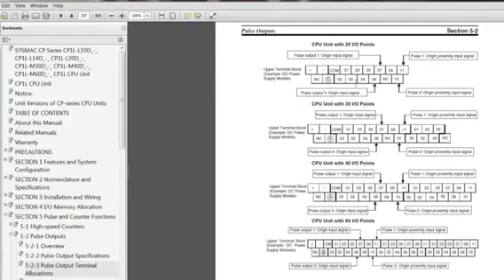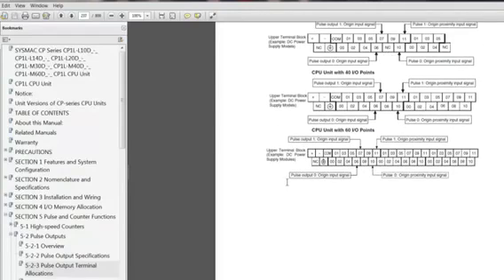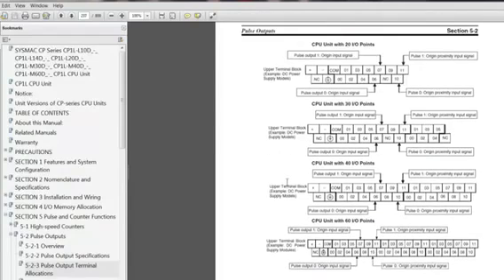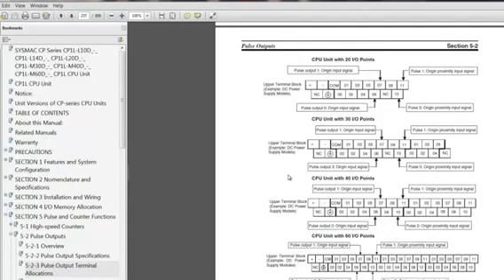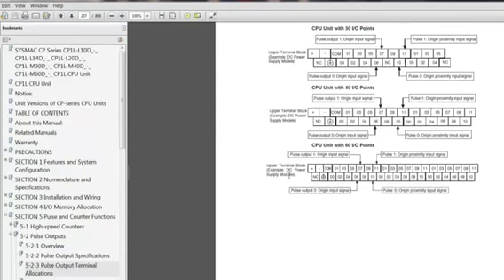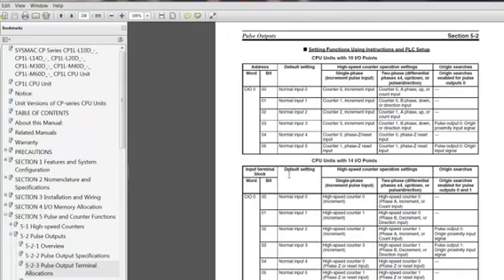Again, with the inputs, your homing inputs and locations of things here do need to be taken into consideration. So, key point here is that as you're buying the I/O system, if you're buying a 20-point PLC and you're wanting to do two axes of motion control, you're probably going to be using four points of output and probably two to six inputs depending on what kind of limits you might have on actuators. So, that will take away from usable I/O and it's as you might expect, but just a good key point there nonetheless.